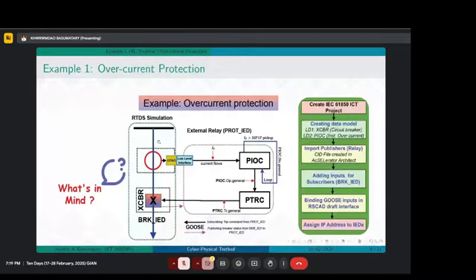Suppose you need a PIOC, instantaneous overcurrent protection logical node, and a PTRC, protection trip condition and breaker status. You select overcurrent pickup PIOC and protection logical node PTRC with circuit breaker status. These data sets will be created in your AcSELerator Architect software.